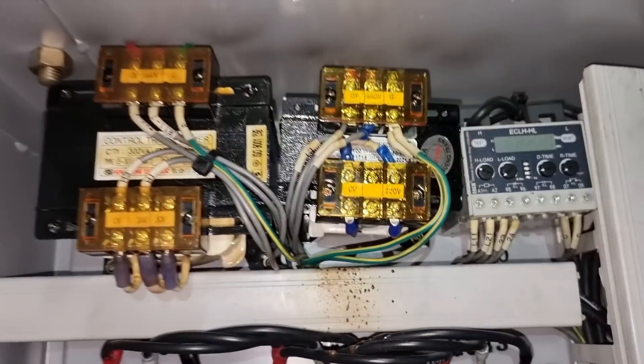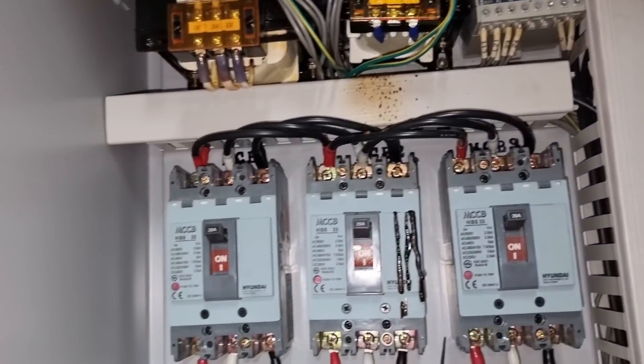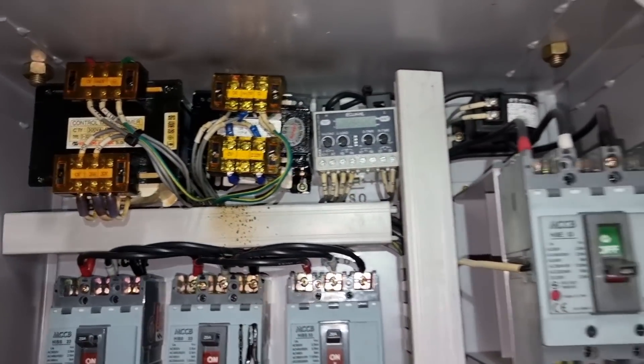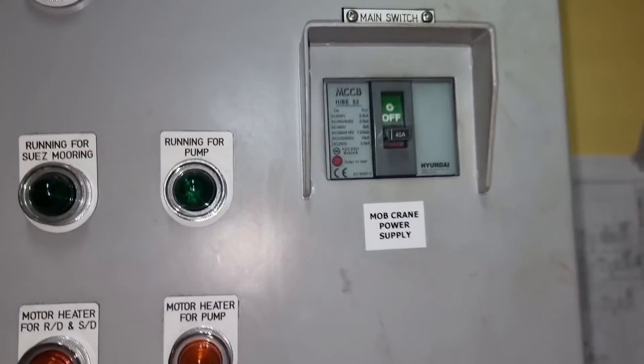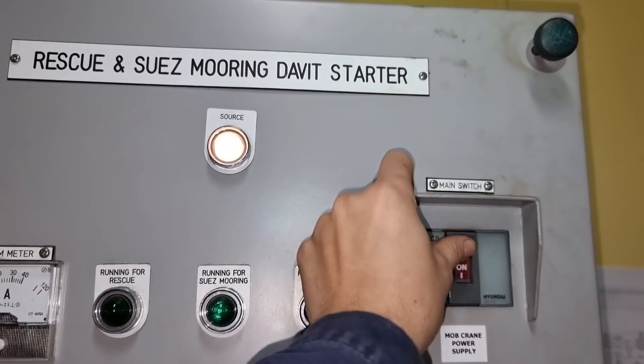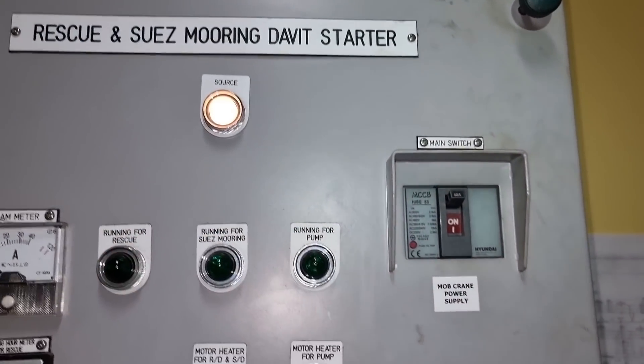As a safety precaution, we need to close the control panel door before powering on the system. The system is not tripping anymore. We found a problem with the heater, we replaced the transformer, and it's working fine now. Let's go outside and see the heater.